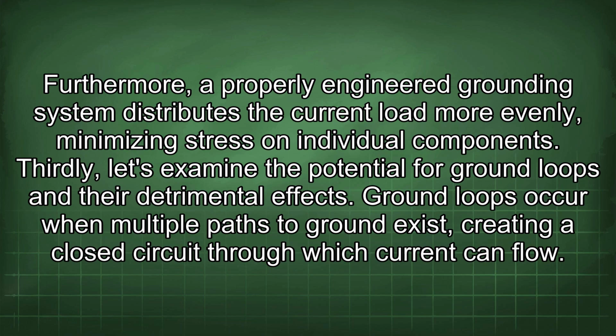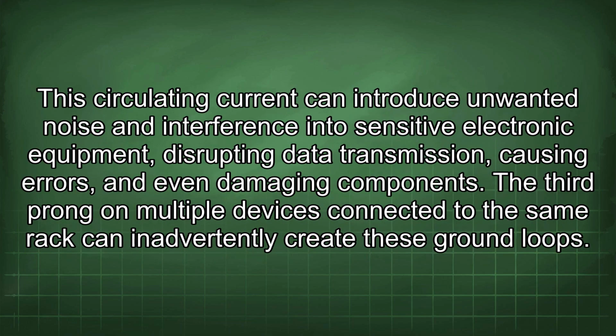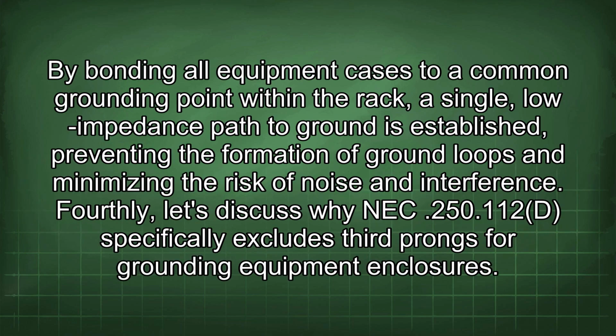Thirdly, let's examine the potential for ground loops and their detrimental effects. Ground loops occur when multiple paths to ground exist, creating a closed circuit through which current can flow. This circulating current can introduce unwanted noise and interference into sensitive electronic equipment, disrupting data transmission, causing errors, and even damaging components. The third prong on multiple devices connected to the same rack can inadvertently create these ground loops. By bonding all equipment cases to a common grounding point within the rack, a single, low-impedance path to ground is established, preventing the formation of ground loops and minimizing the risk of noise and interference.